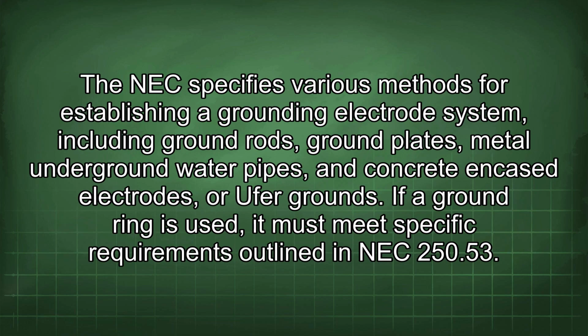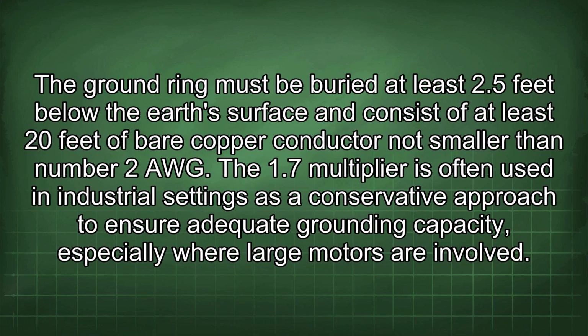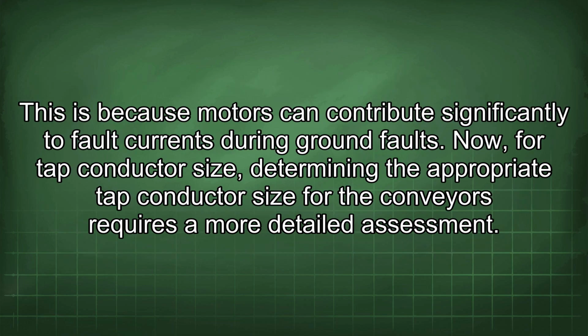The NEC specifies various methods for establishing a grounding electrode system, including ground rods, ground plates, metal underground water pipes, and concrete encased electrodes, or Ufer grounds. If a ground ring is used, it must meet specific requirements outlined in NEC 250.53. The ground ring must be buried at least 2.5 feet below the Earth's surface and consist of at least 20 feet of bare copper conductor not smaller than number 2 AWG. The 1.7 multiplier is often used in industrial settings as a conservative approach to ensure adequate grounding capacity, especially where large motors are involved. This is because motors can contribute significantly to fault currents during ground faults.